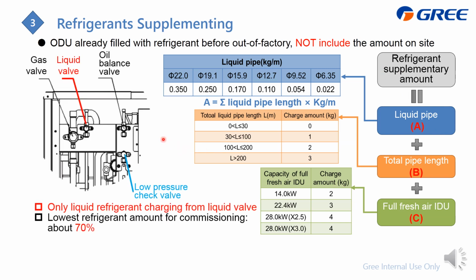To charge is very easy. Here is the view of the outdoor unit piping. This is the gas valve of the outdoor unit, the liquid valve, the oil balance valve, and this is the low pressure check valve. We require charging liquid refrigerant. Charge liquid refrigerant only from the liquid valve, only into this one, and the amount is about 70%.